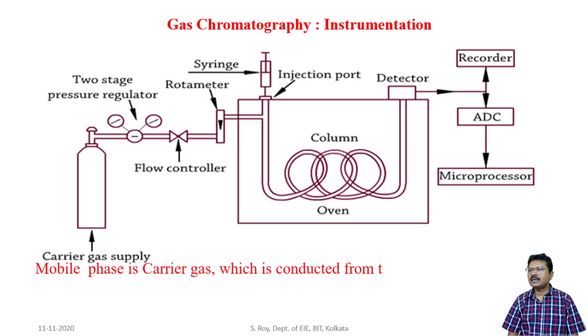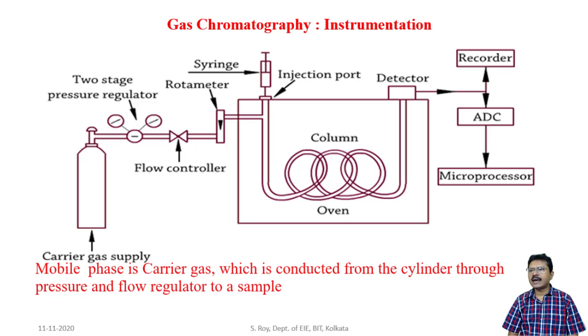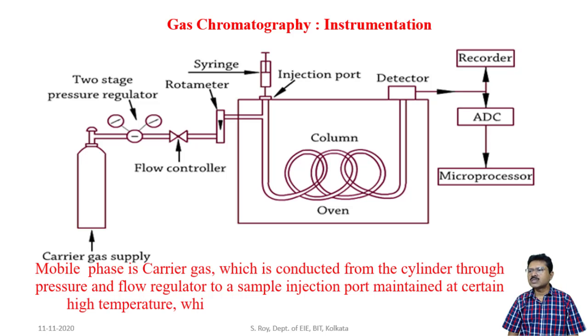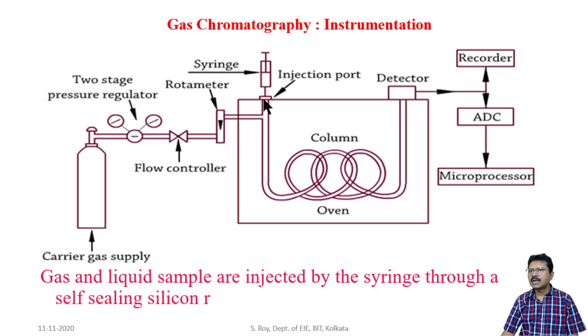The mobile phase — carrier gas — is conducted from the cylinder through a pressure and flow regulator to a sample injection port maintained at a certain temperature, which ensures rapid vaporization of the solute. These arrangements — pressure regulator, flow controller, and rotameter — are used to maintain a particular control of the carrier gas supply and to monitor its flow.